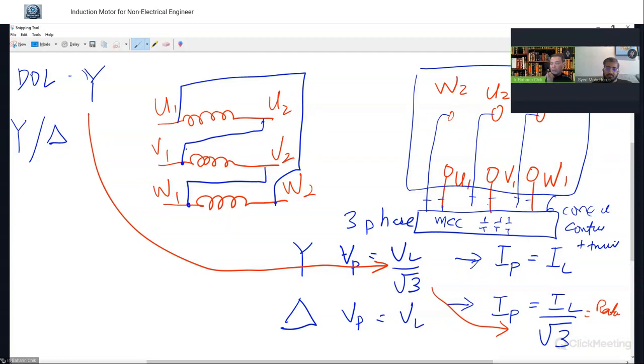So we need to do the studies. When we do the network studies, we see that when we start the motors in DOL, which is the cheapest control scheme, it gives a very high voltage dip in the system. So when there is a voltage drop, it will affect all the running motors. So we will have an issue on that. Once those issues crop up, then they will look into several solutions.